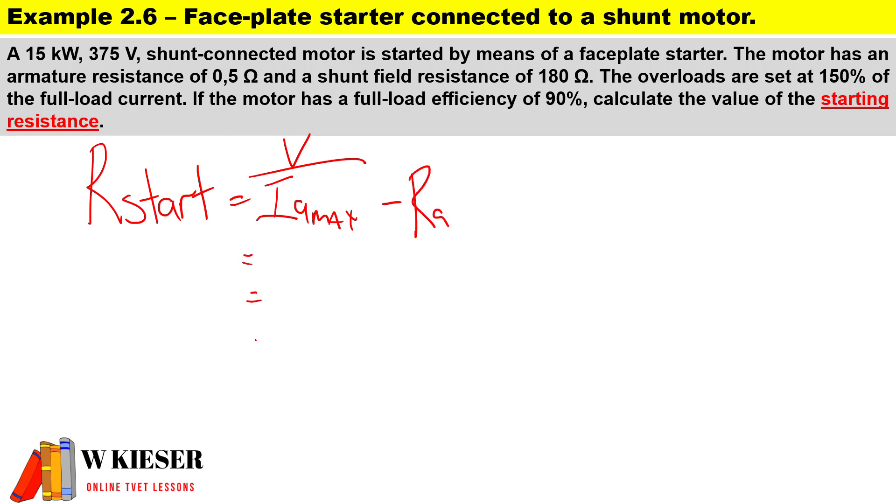That's basically the formula we'll use to answer this question, and we'll obviously need to calculate Ia max. If you have a look over there, our overloads are set at 150%, so that's 150 over 100 times how much current. So we still need to calculate armature current as well. We'll come back to these calculations. First of all, we need to calculate the armature current.